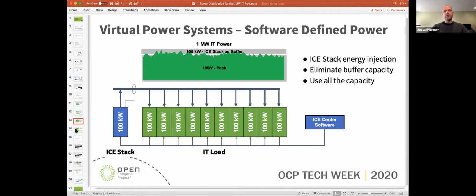In most cases, when we make this change, the peak load can be driven up to the limits of the physical infrastructure, and any power above that's provided by the energy storage system. So for this example, we've recovered 10% of the system's capacity, and now this 1 megawatt row truly has 1 megawatt of capacity for 1 megawatt of load.